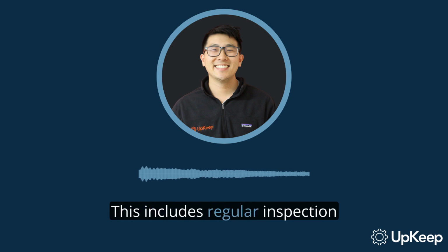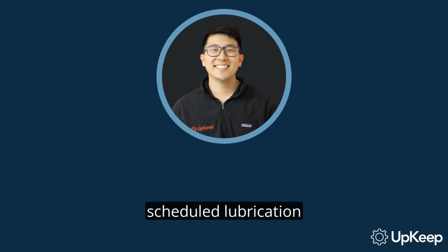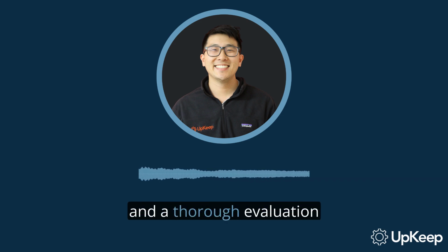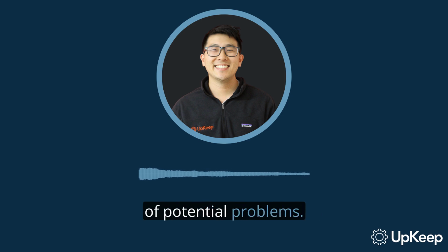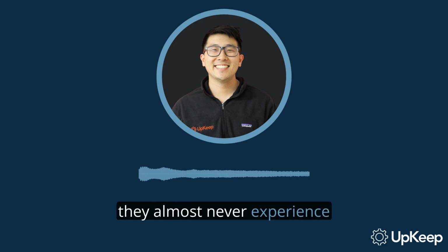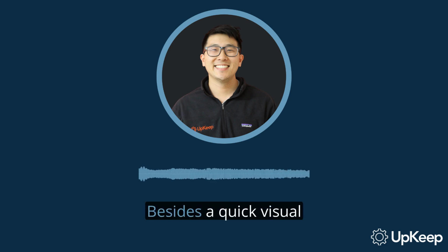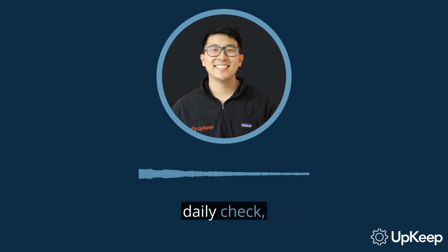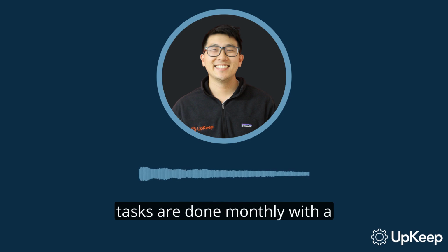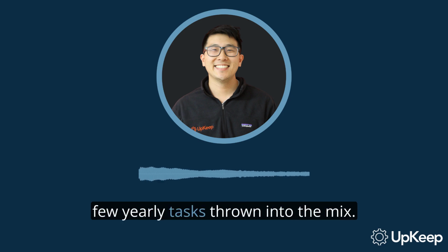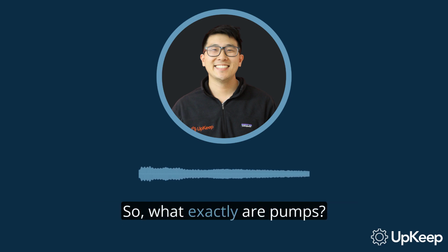This includes regular inspection for stability and balance, scheduled lubrication, and a thorough evaluation of potential problems. When pumps receive this kind of proper maintenance, they almost never experience a catastrophic failure. Besides a quick visual daily check, most preventive maintenance tasks are done monthly with a few yearly tasks thrown into the mix. So what exactly are pumps?